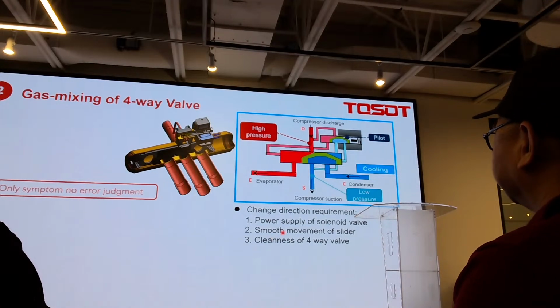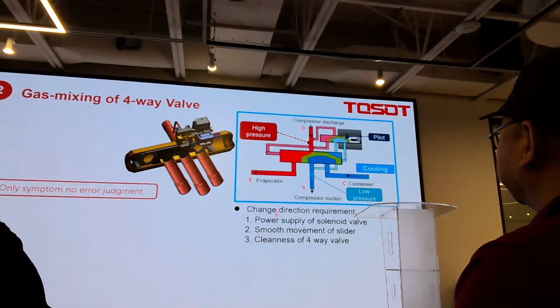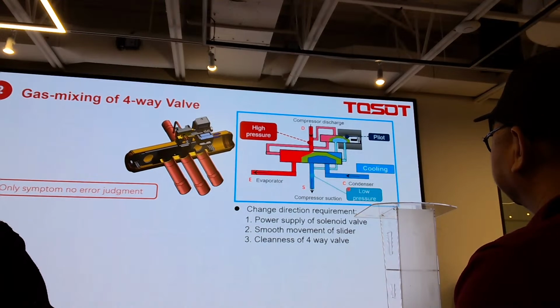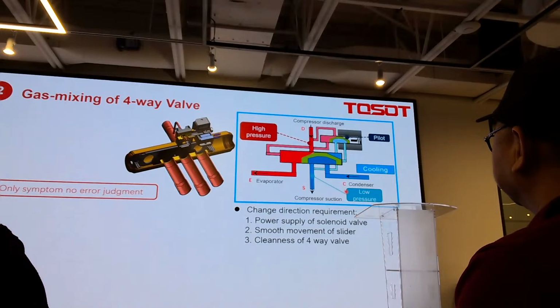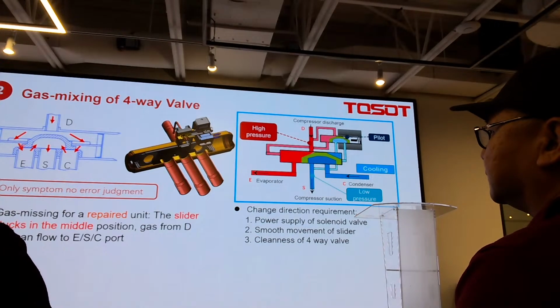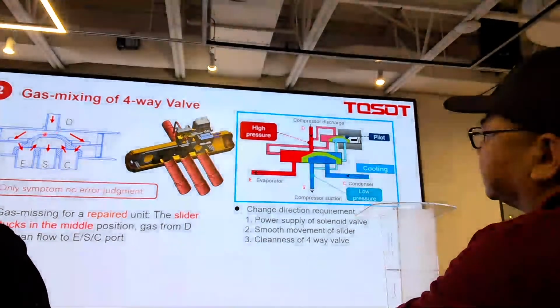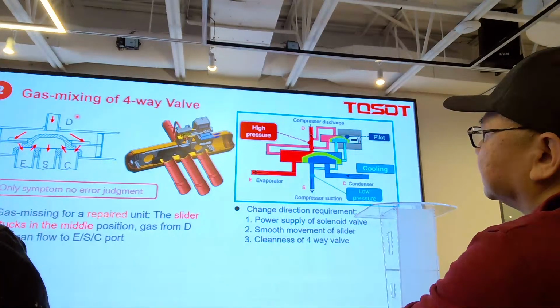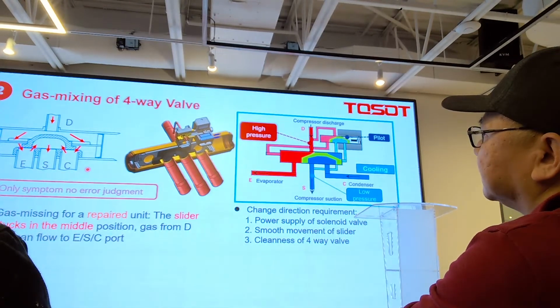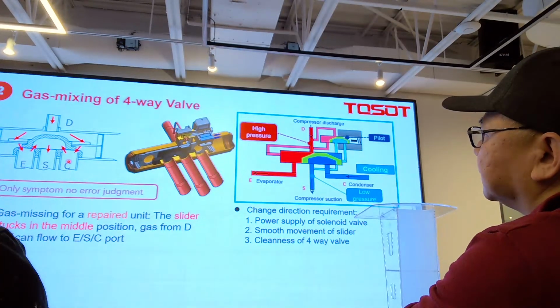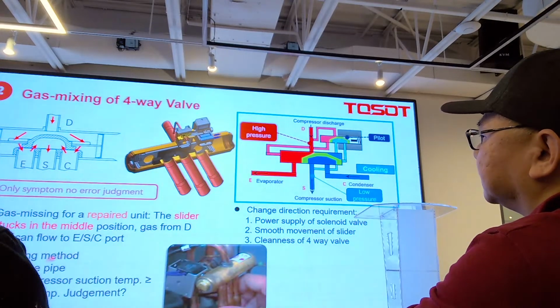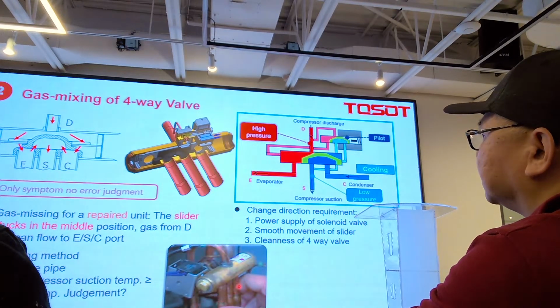So on site, if you have a unit that is not cooling and heating, first, you can identify it by checking the temperature between this E and C. If it is normal, the temperature difference should be huge. If it is almost the same, that means it is malfunction. Malfunction means the slider inside is stuck in the middle, and then the refrigerant from the compressor cannot flow into the E or C. That means the E or C tube temperature is almost the same. And just like this one, you can just feel these two pipes.